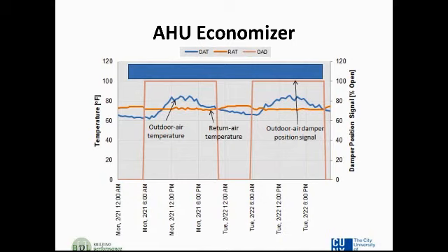All right, let's look at another example, looking at the possibility for economizing with your air handler. Taking a look at this trend chart, you can see that we have basically a 2-day period here. You can see from the pink line, that's the outdoor air damper that opens and closes. It looks like it's open during operating hours and closed otherwise. It also looks like your outdoor air temperature in blue is getting pretty warm during the day. It's in the low to mid 80s during the day. And your return air temperature looks about right, low to mid 70s. The question is, is there an opportunity here to economize, to use free air cooling? If you look carefully, the answer is yes.